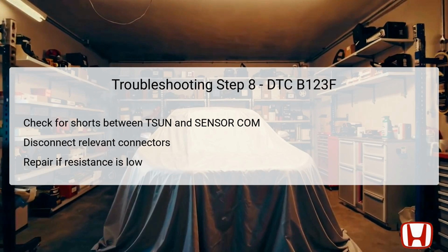In Step 8, you will check for shorts between the T-Sun and sensor COM lines. Keeping the climate control unit connector A32P and the sunlight sensor 2P connector disconnected, measure the resistance between the designated test points. Again, you should find a resistance reading of 1 megaohm or more, which indicates that there are no shorts present in this wiring pair. If the resistance is less, this shows a short between the T-Sun and sensor COM wires, necessitating immediate repairs to rectify the issue.